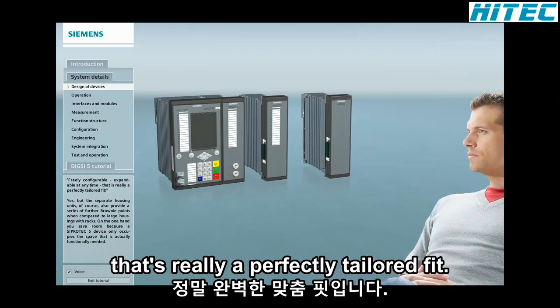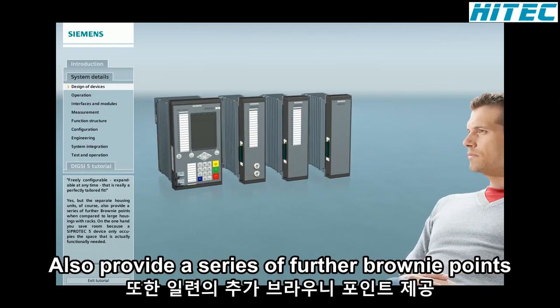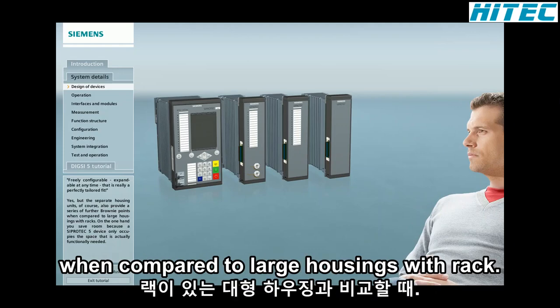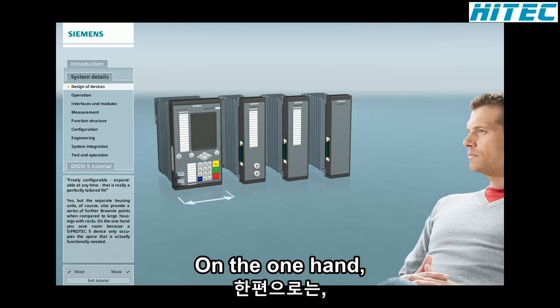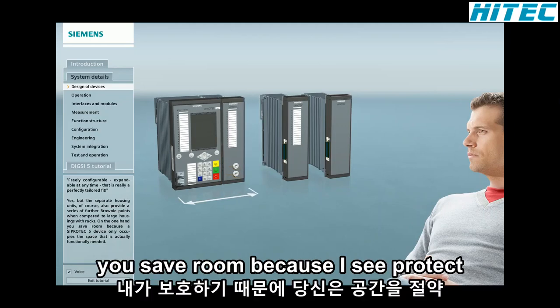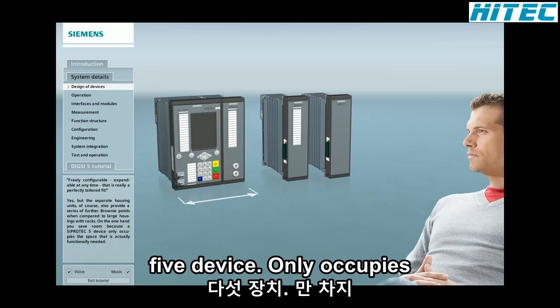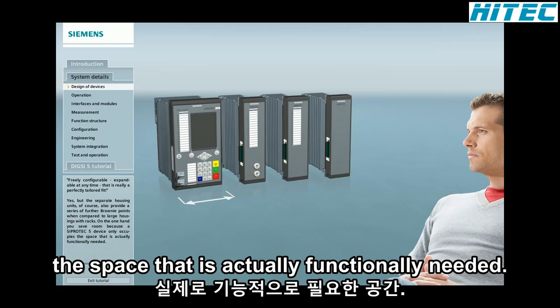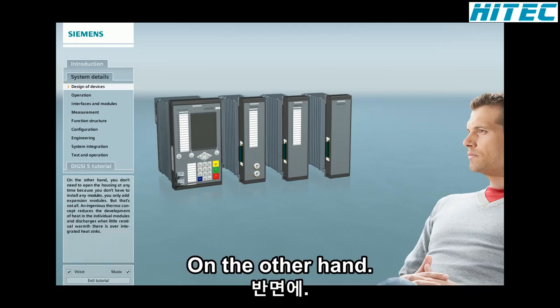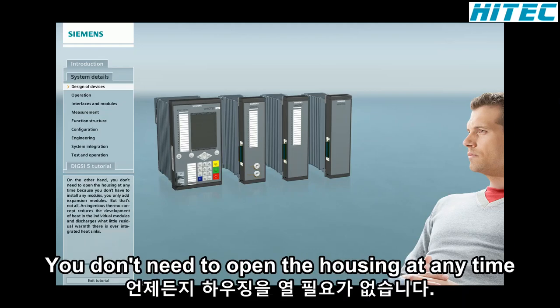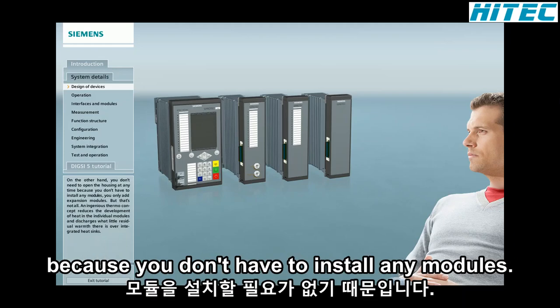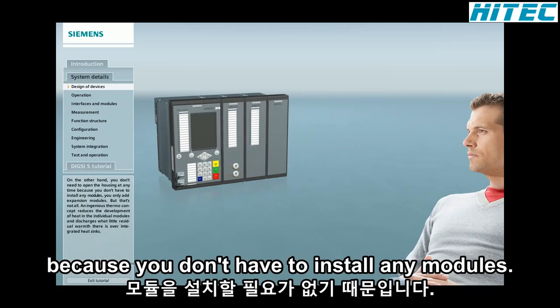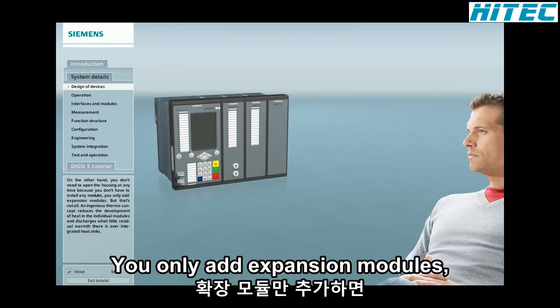Yes, but the separate housing units, of course, also provide a series of further brownie points when compared to large housings with racks. On the one hand, you save room because a SIPROTEC 5 device only occupies the space that is actually functionally needed. On the other hand, you don't need to open the housing at any time because you don't have to install any modules, you only add expansion modules.